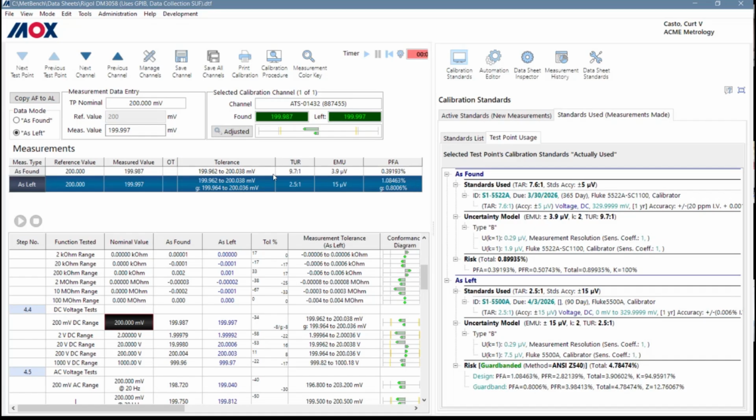Okay. Now, what's important about this is that MPS then automatically guard bands, and guard banding is optional in MPS. So if you don't want any guard banding, you can basically turn off guard banding. And if you do want guard banding, MPS supports 3 methods. It supports the old RP10. If you're familiar with MET/CAL, for instance, it used the RP10, which is just a fixed percentage of the EMU that will be the guard band amount.